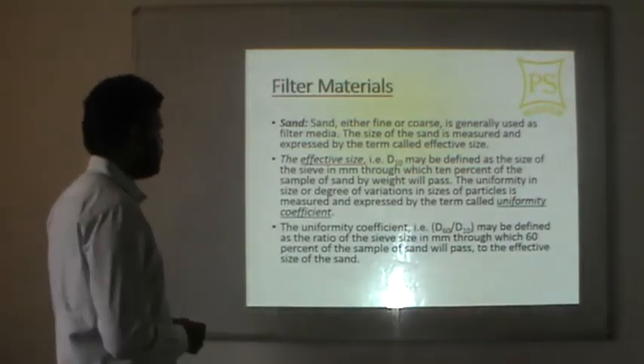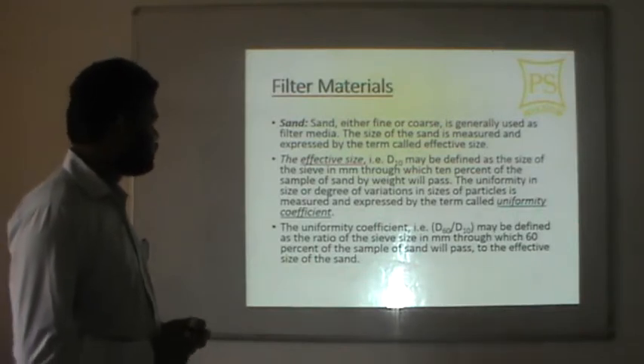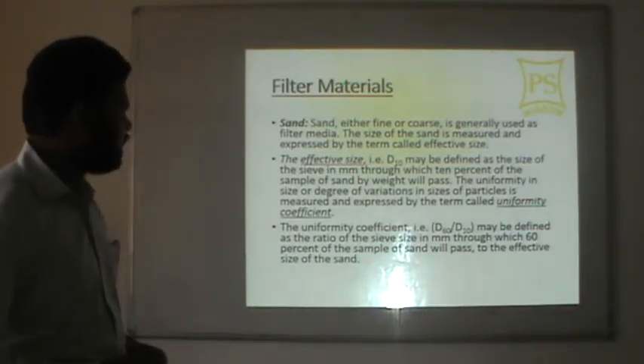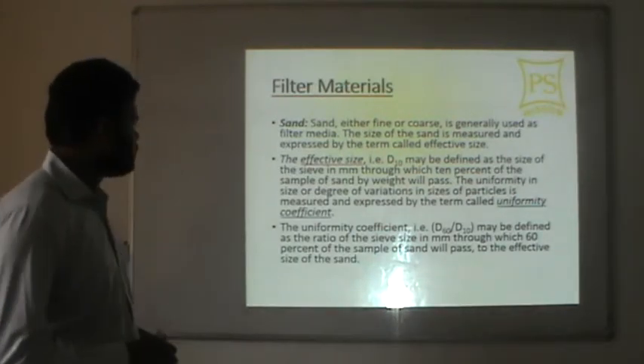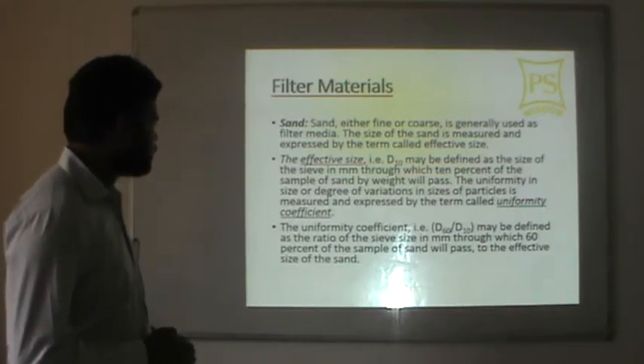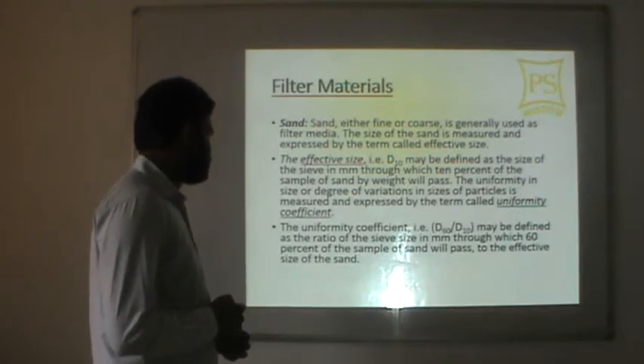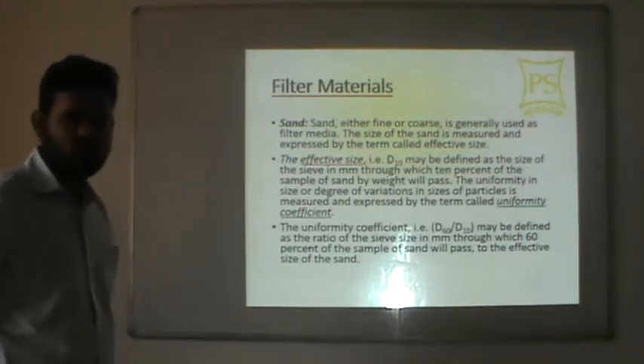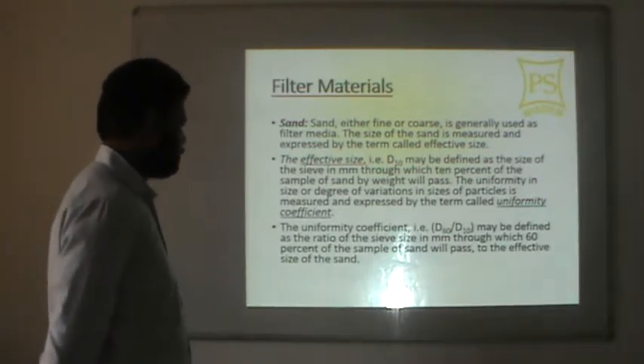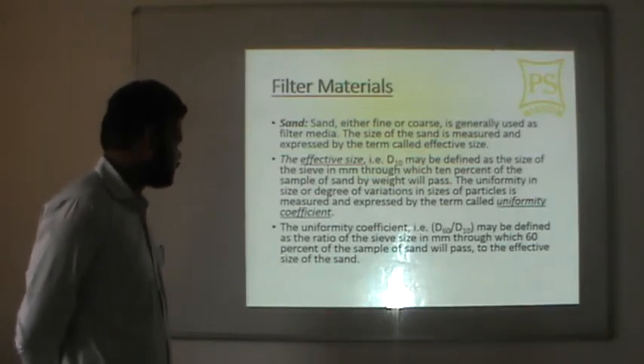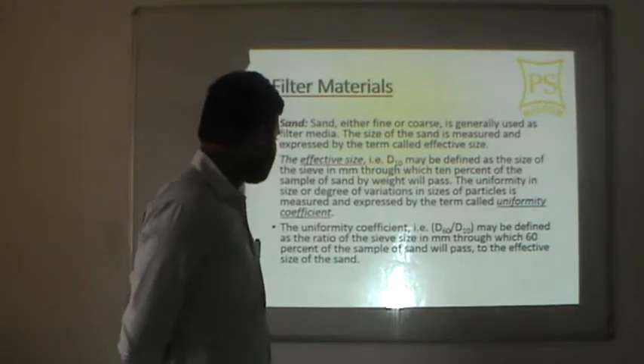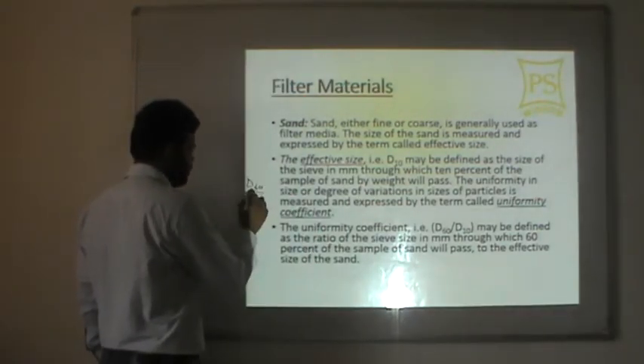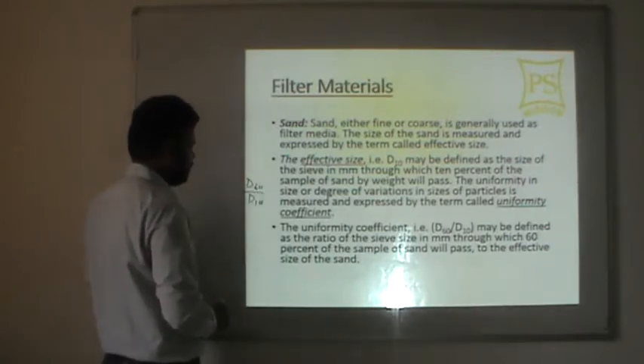Filter materials: sand, either fine or coarse, is generally used as filter media. The size of sand is measured by the effective size, d10, defined as the sieve size in mm through which 10% of the sand sample by weight will pass. The uniformity coefficient is d60/d10, defined as the ratio of the sieve size through which 60% of the sample will pass to the effective size d10. Effective size is d10 and uniformity coefficient is d60/d10.